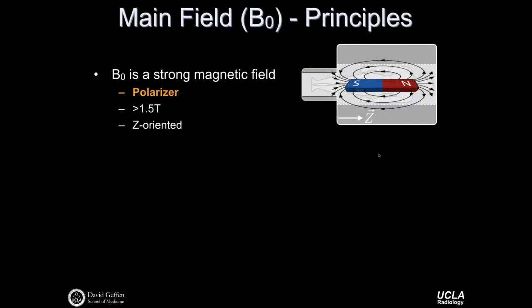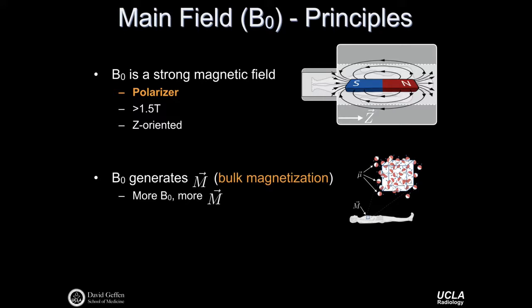The B0 field is a strong magnetic field. On the right-hand side is a cutaway of an MRI scanner. We conventionally assign the z-axis to correspond with the long axis of the scanner, and the magnetic field itself is north-south oriented along that same z-axis. The function of B0 is to serve as the polarizer, preparing individual magnetic dipoles to form coherent bulk magnetization. Typically, the B0 field is greater than 1.5 Tesla for clinical imaging systems, and 3 Tesla systems are very common. The larger the B0 field, the larger the bulk magnetization.